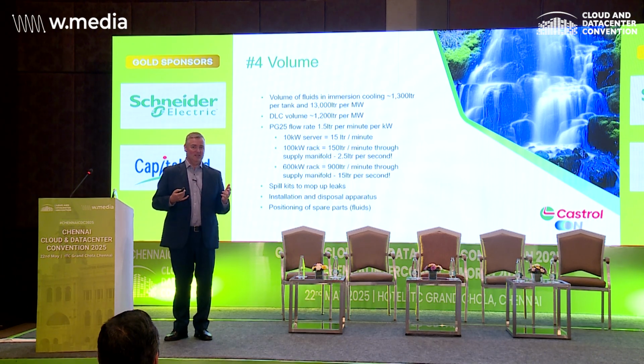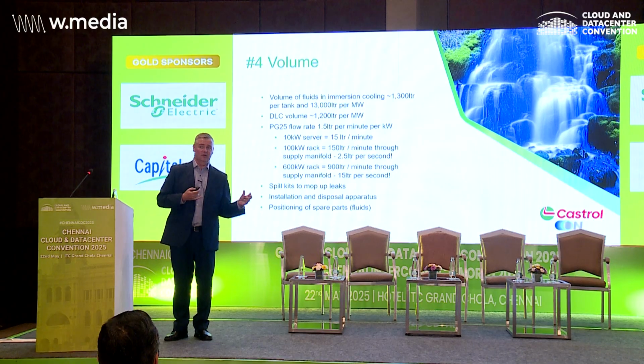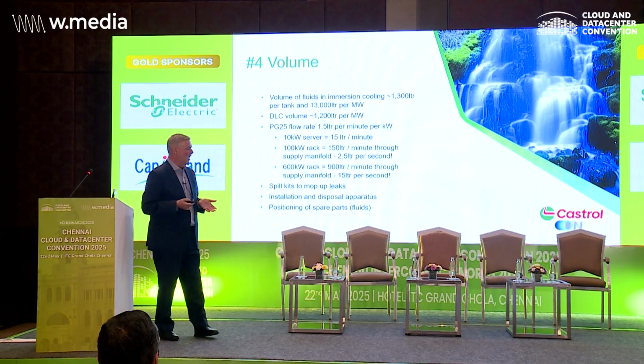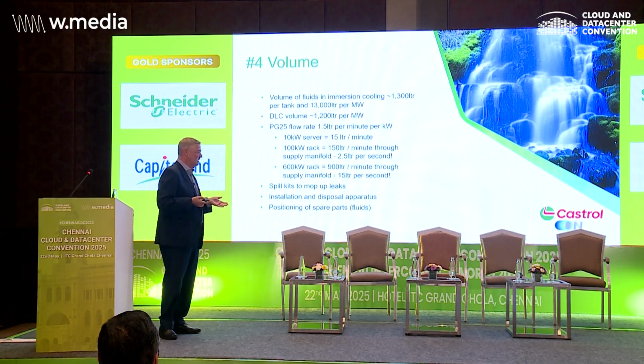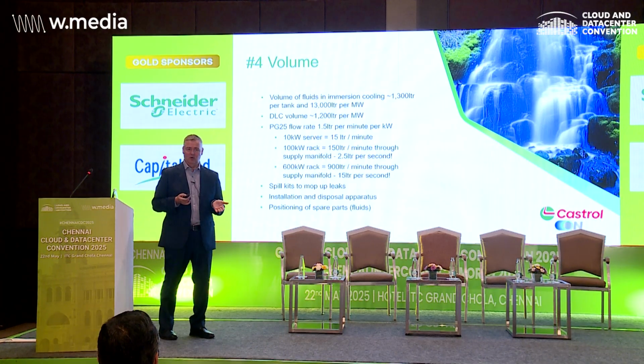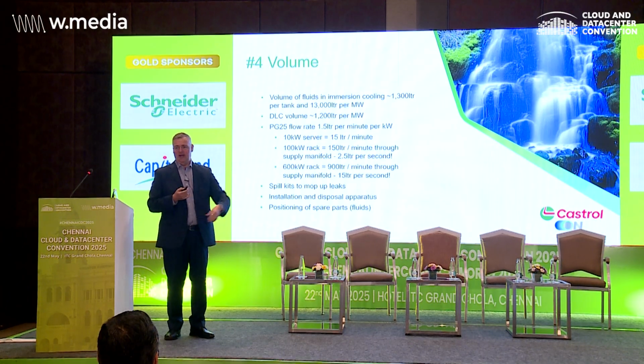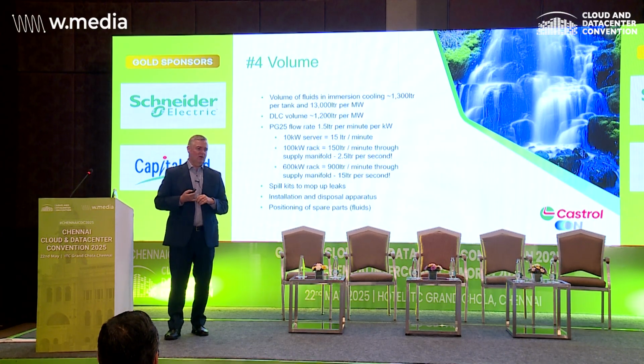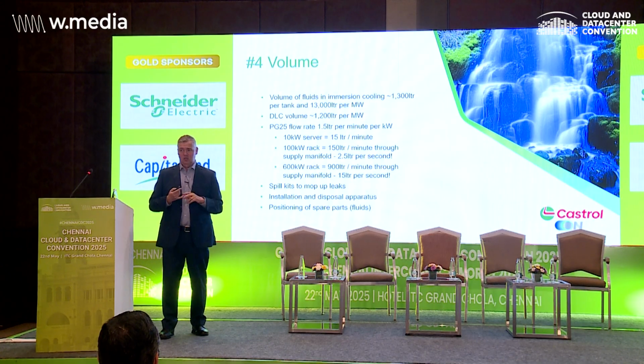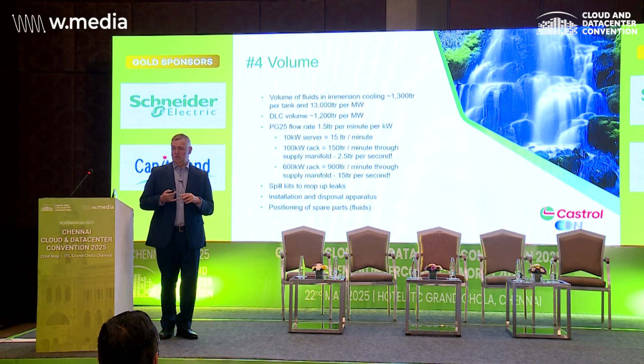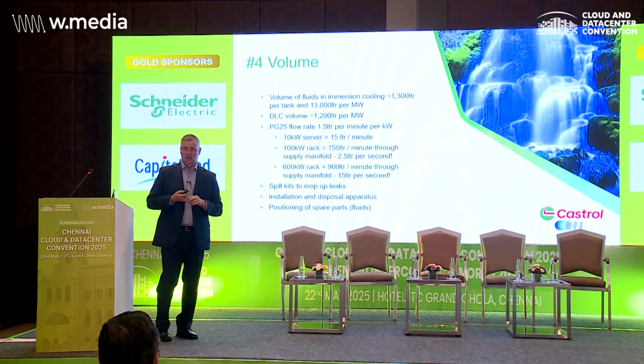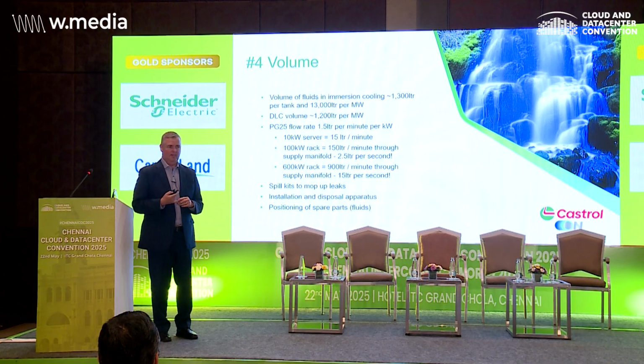So make sure we do that. People often don't realize there's actually a lot of fluid in a data center. When we're talking immersion, we're talking about roughly 1,300 liters per 100 kilowatt tank. When we extrapolate that out, that's about 13,000 liters of oil, although it's dielectric, in a megawatt facility. That's something we need to start thinking about.